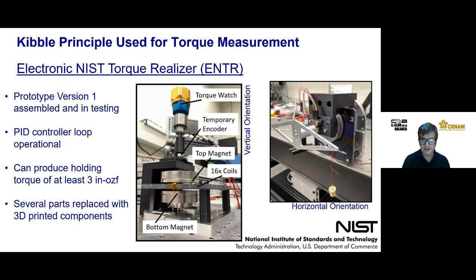The problem with torque at the moment is you're relying on a length measurement and a mass measurement, both relatively simple, but you're also relying on a mechanical apparatus to multiply the length by the mass, and you don't really know how well that's working. This gives you a direct torque, directly traceable to a kibble balance principle. So this is a step forward in terms of reliability of torque measurement.